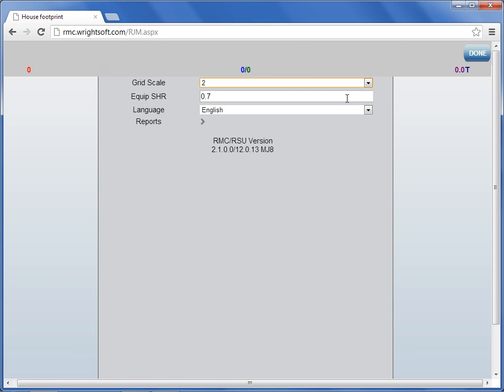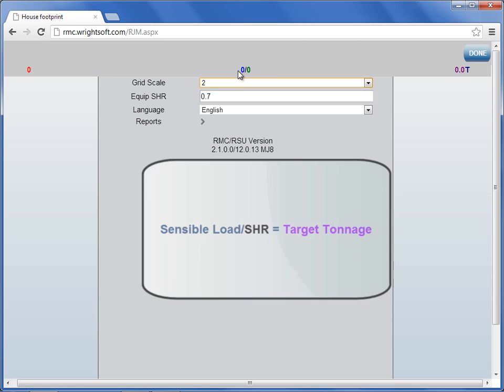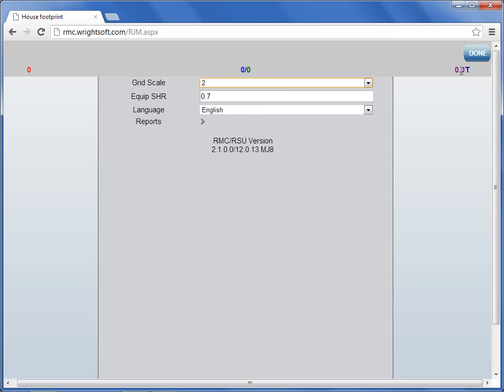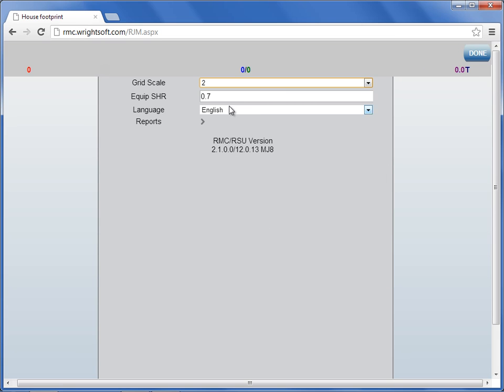The next row is your equipment sensible heat ratio. This controls your target tonnage in the upper right hand side. The sensible load at the top in blue is divided by the equipment sensible heat ratio to determine the target tonnage in the upper right hand side. As you adjust this number, the tonnage will change.